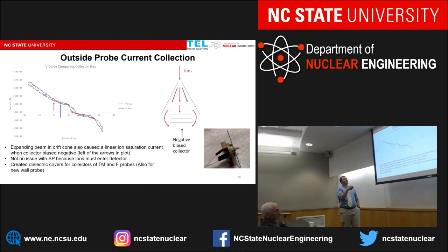So what we realized is, when we made these cones, we always assumed the beam would come straight down and we'd collect it and it'd be great. But a traditional particle beam expands as it travels. The ion expansion caused ions to actually travel around the detector. And because the probe was just in the cavity, there was nothing to stop the ions from swinging around the probe and getting collected by the collector on the sides. So we made a quick cover to cover up the collector and fix this little issue.